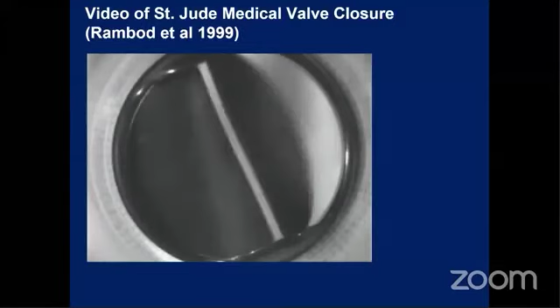I'm going to show you a little bit of film of what happens. This is looking at this bileaflet valve from downstream, and I'm repeating it many times here. And you see these clouds of bubbles that are generated at the very last moment of closure. That's difficult to deal with in terms of the blood damage to the red blood cells. Human hearts are flexible. This material is not flexible. When it's flexible, the collapse is much less, the closure is much less violent and there is much less damage. And so that's why the pig valves, for example, are still preferred to these solid surface valves. We're not very good, really, at designing structures like this with flexible materials, and that remains a problem and an issue.